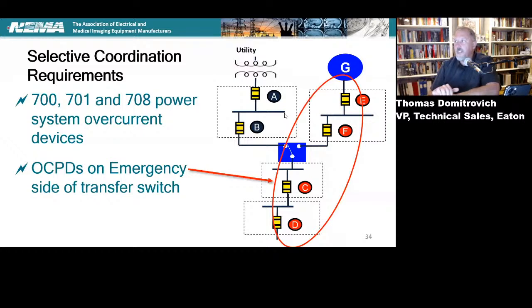And panel 13 would say, they're not under our purview. They're not part of the system. And then someone would say, well, you need to say that they don't need to selectively coordinate. And they'd say, well, that's outside of our purview. We don't have any purview over that. They have purview over the devices that are circled. And the way the code reads, device D has to selectively coordinate with everything upstream, which includes B and A. And C has to selectively coordinate with everything upstream, which includes B and A. But B and A do not have to selectively coordinate with each other, per the National Electrical Code. That could be a design decision by the design engineer.